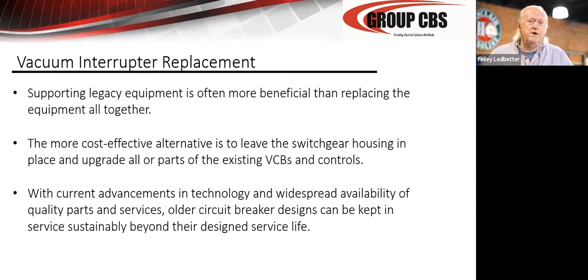If it's powering the parking lot lights, maybe you can afford a failure there, as long as it doesn't damage the equipment, smoke up the equipment, shut down a critical circuit, or hurt somebody. With current advancements and widespread availability, these vacuum interrupters are out there. There are several manufacturers building replacement interrupters. You can still go to the manufacturer and get both of them. You need to have them tested.